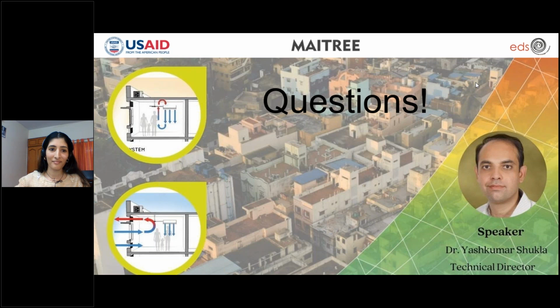And that's an excellent question. And this is a question that we often get when we talk about natural ventilation. It's a fair understanding that it's very challenging when you are using natural ventilation to maintain the indoor air quality. There are several approaches to do that. Of course, just keep in mind that air quality is a dynamic parameter. It does not stay constant throughout the year. So there will be periods of the year when air quality is moderate, which you can use for natural ventilation. When air quality is not good, of course you have to incorporate that in your control algorithms. You cannot just operate windows when outside is extremely bad. You need to balance between the ventilation rates as well as maintaining the indoor air quality.